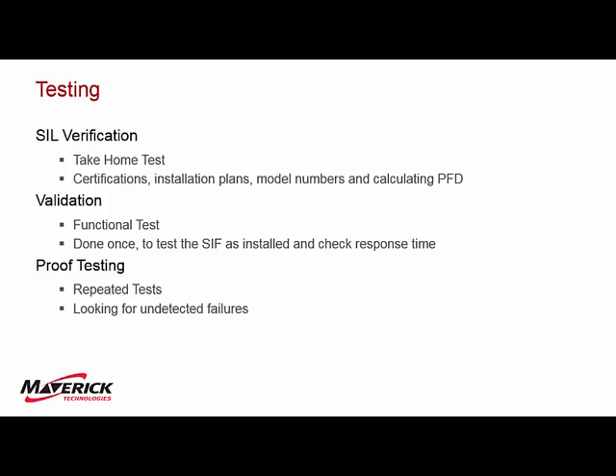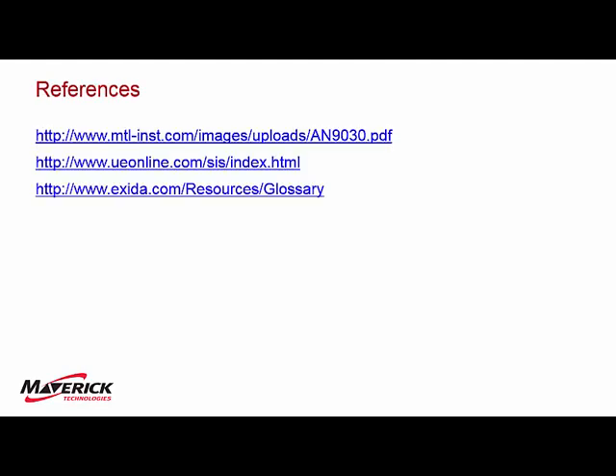And lastly is the routine testing. The proof testing is repeated tests. What you're looking for in a proof test is those undetected failures, that level switch that got stuck and isn't going to tell you when the tank's about to overfill. Some companies do proof testing on individual components. They'll test their sensors at one rate and their valves at another. Some companies do a full validation test periodically and consider it a proof test. So that's kind of a company preference. Material-wise, that's kind of all I wanted to cover. The references, I'm going to post this presentation to the SIS-SME website. These are a couple of good references. This MTL reference is really good at explaining the terms. That's where I got most of the definitions. So that's all I've got. Do you all have any questions?